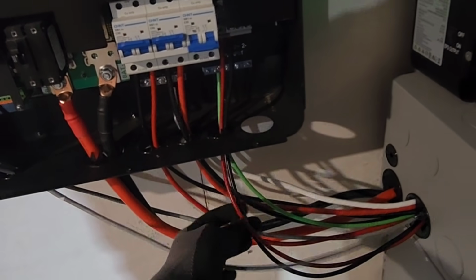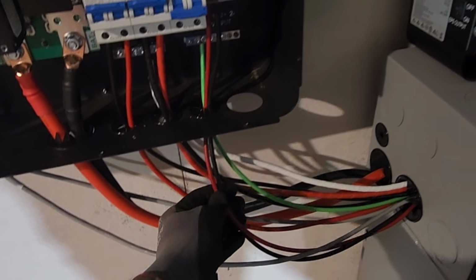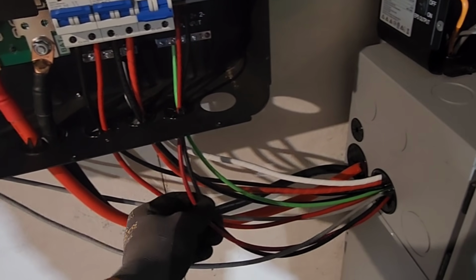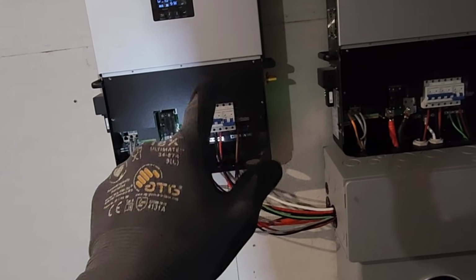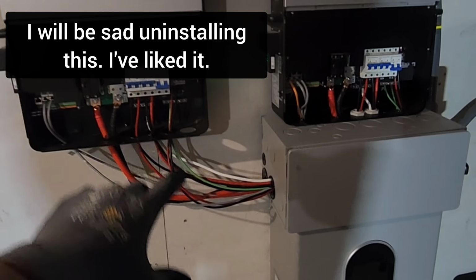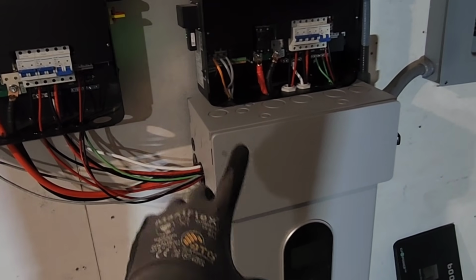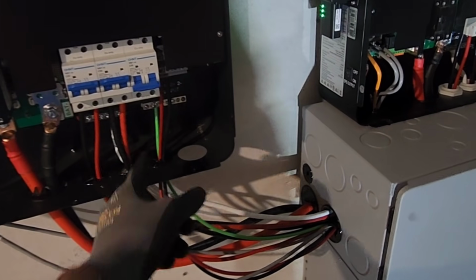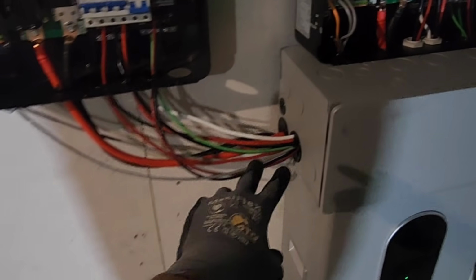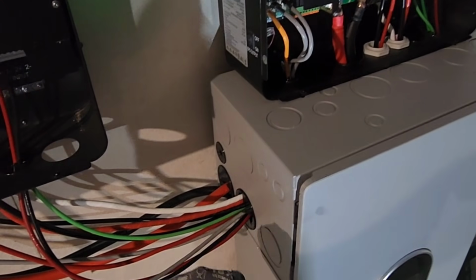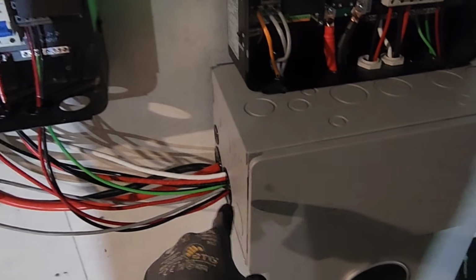Obviously this won't pass inspection, especially the solar portion, because high voltage DC solar needs to be in metal conduit as far as code goes. I'm going to test this out real quick, then I'll be putting in a different inverter. But if I were keeping this system in place permanently with only one battery, I'd have a long wire chase, get rid of this thing, and have everything enclosed in metal. If I had two batteries, with one under here, I could have two of these boxes with metal conduit in between the two units, so everything would be encased in metal.